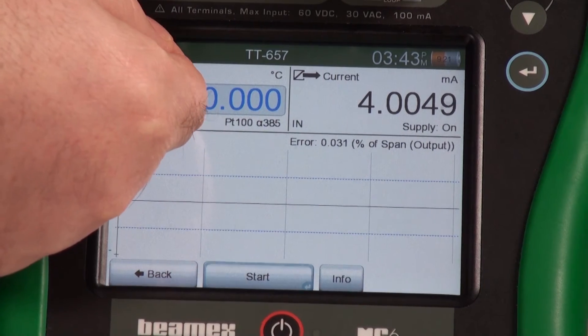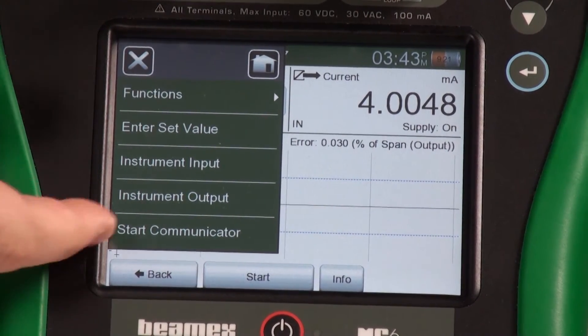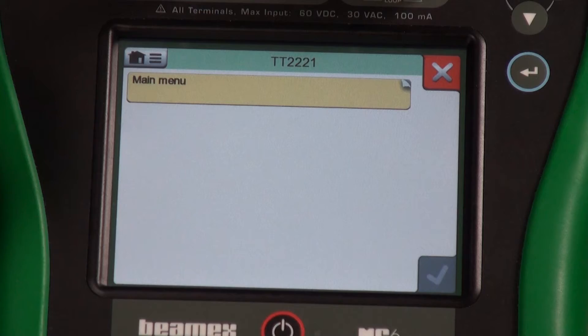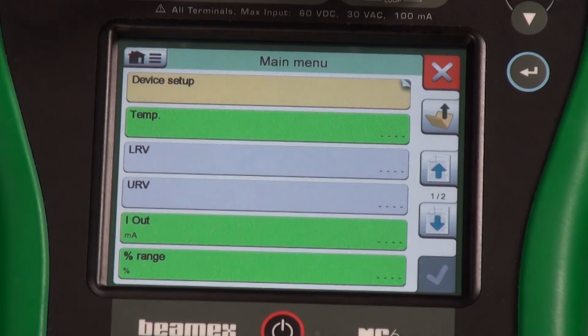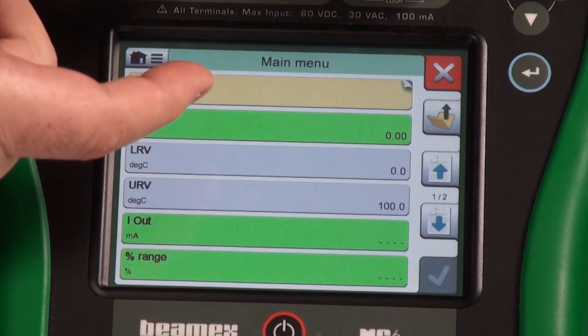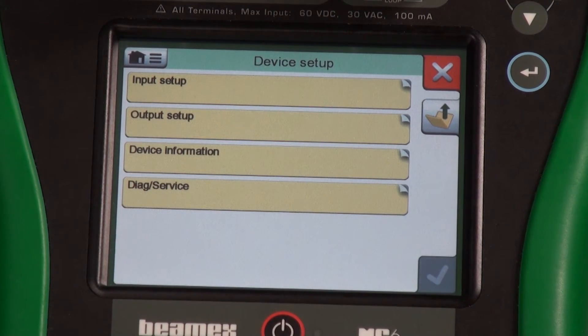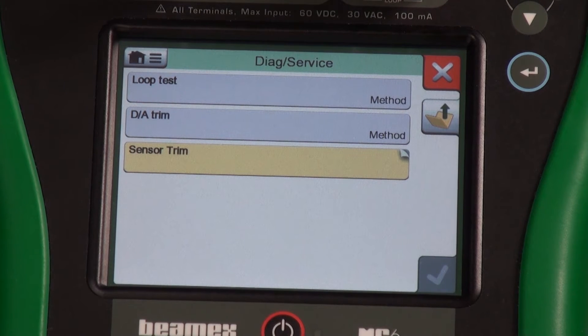To do an adjustment, we need a communicator to talk to this HART device. Here's the secret — the top left-hand button. There's an option here to start communicator. By selecting that, it is now firing up the HART communicator to speak with the transmitter. From there, we'll have access to the different trimming functions. We found the device, and in this device we want device setup. Every manufacturer will be a little bit different, but with this manufacturer it's under Diag Service. We have a D-to-A trim and a sensor trim — the sensor trim is the A-to-D trim, so we need to do both of them to do a proper calibration.